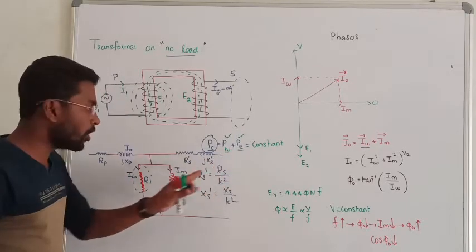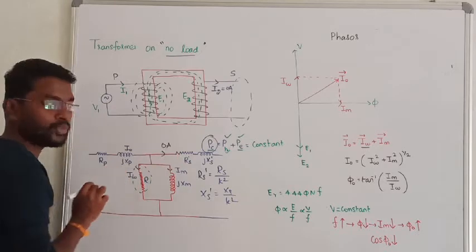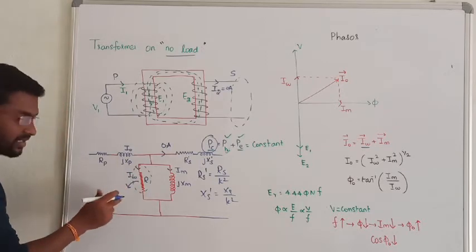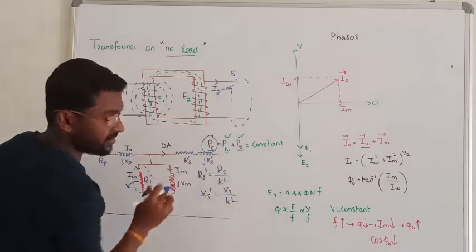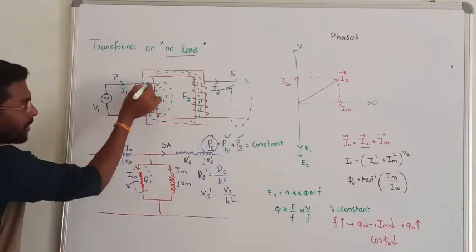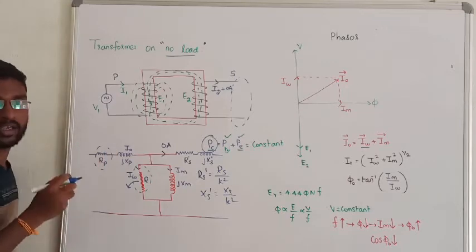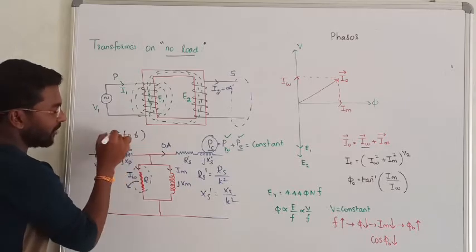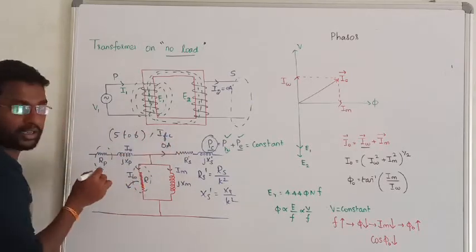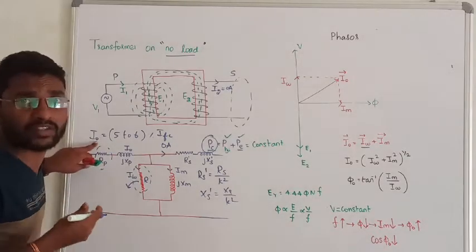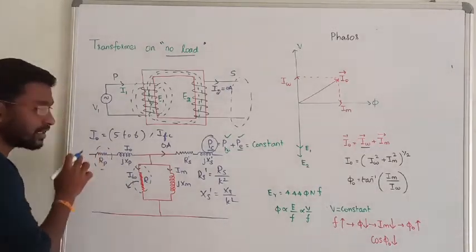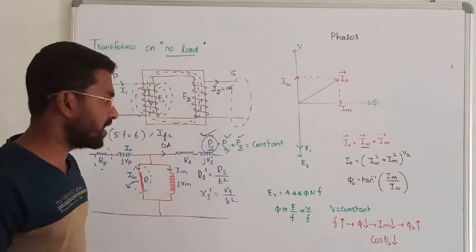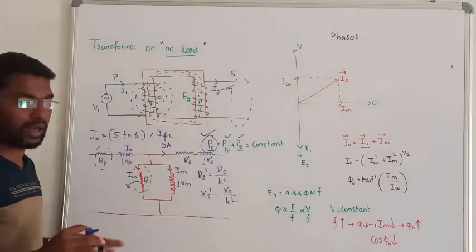Under no-load, the secondary current is 0 amperes. In the primary equivalent circuit, the core resistance offers hysteresis and eddy current losses. There will also be copper loss in the primary winding, but since the no-load current is very small — approximately 5 to 6% of full load current — the copper loss is also very small and is usually negligible. So under no-load, we consider only core loss; copper loss at no-load is ignored.